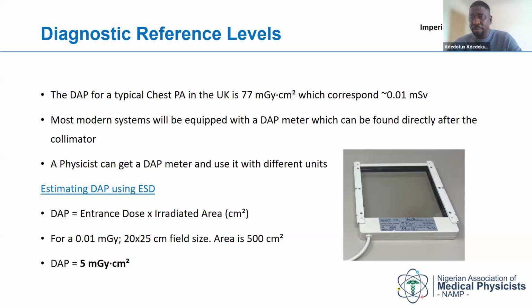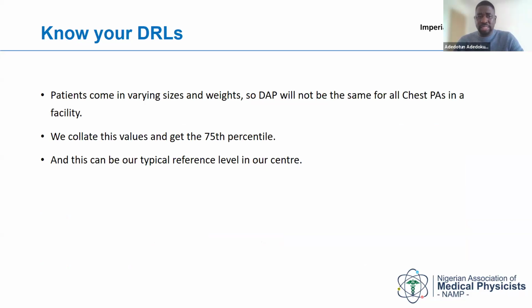We have our dose meter, and you can measure your air kerma easily. You have that in milligray, and then you can multiply that by the field size. That gives you what your DAP is going to be. It is possible to do this manually. Like I said, patients come in varying sizes and weights, so your DAP is not going to be the same for all the chest PAs. But if you collate all of the values, then you get your 75th percentile. That can be your local DAP.